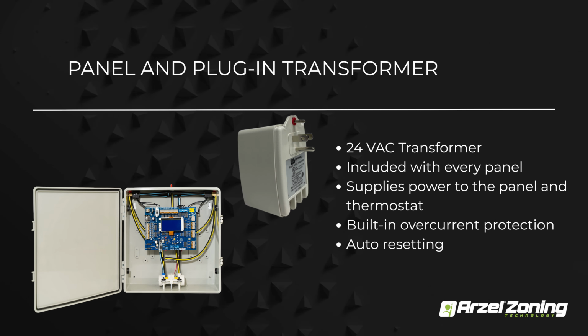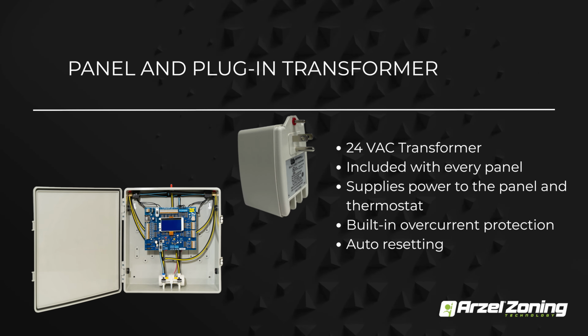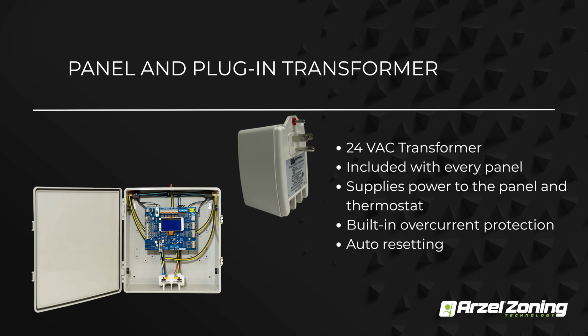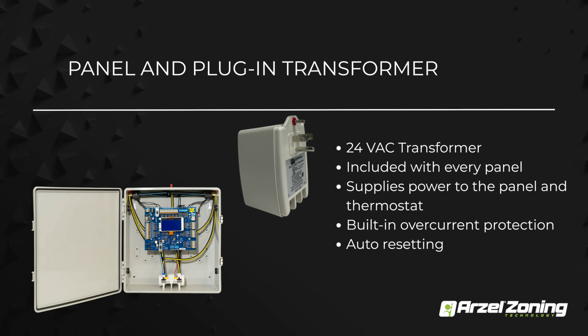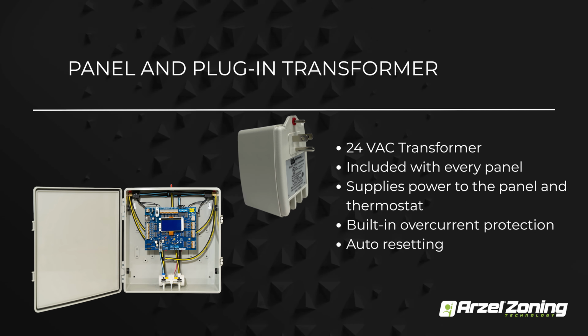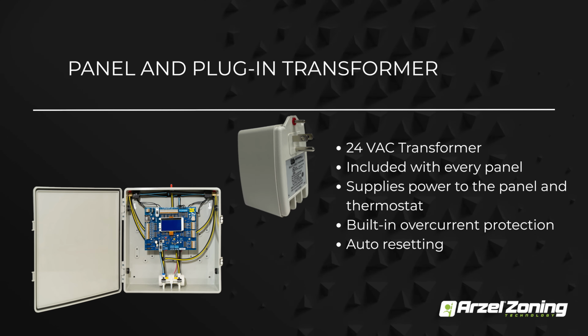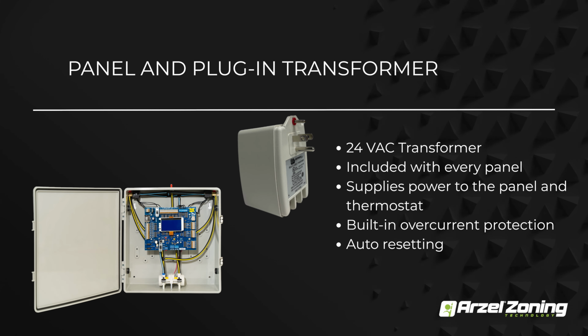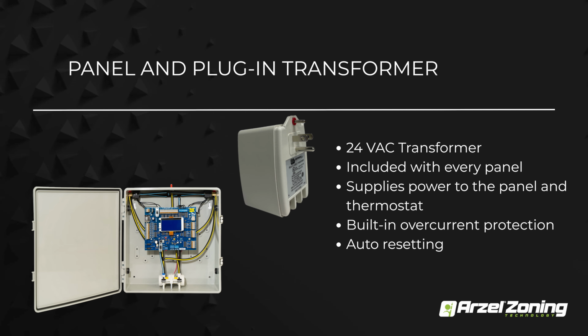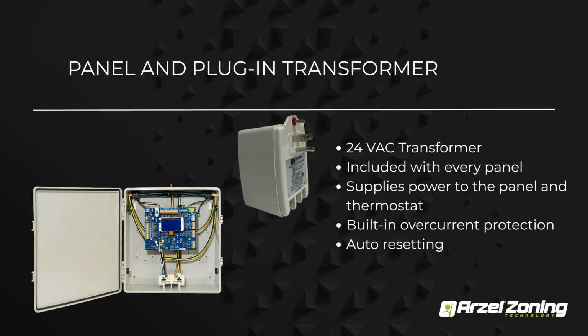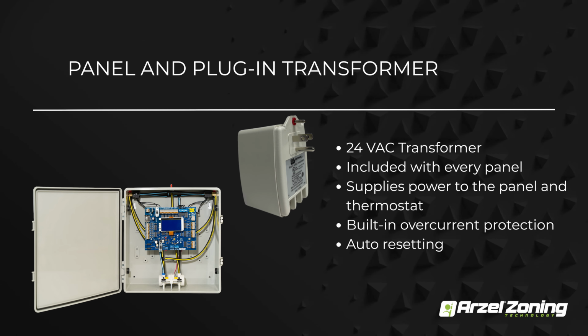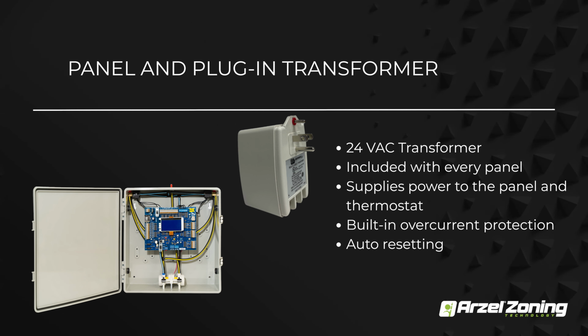So with our panels, they're all going to come with a plug-in style transformer, and this is going to power up your panel, and it's also going to supply power to each of your thermostats in that system as well. So typically any 4-zone or under panel is going to ship with a plug-in 40 VA transformer, and that's going to supply that voltage for you. And it also does have a built-in auto resetting fuse. So if you guys have a short in the system, it'll actually drop your secondary voltage out of the transformer and prevent any damage to the equipment or the Heat Pump Pro or whatever zoning panel you have.